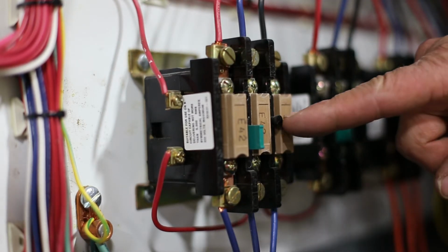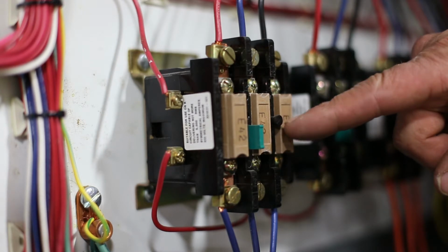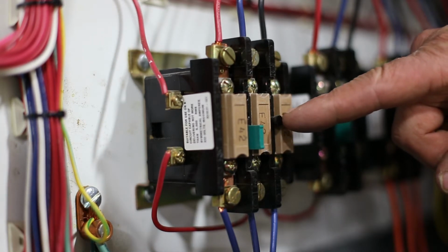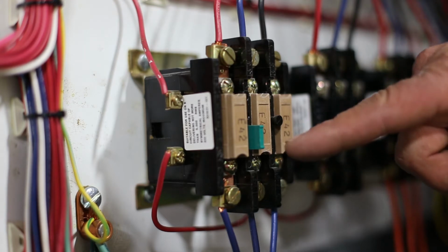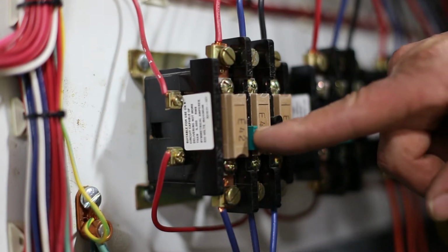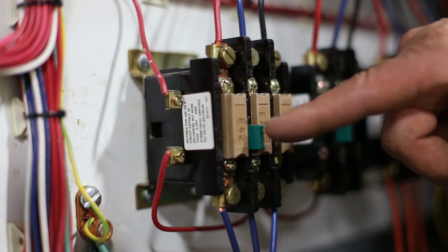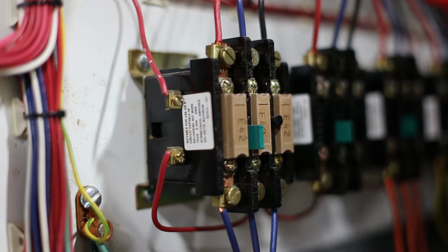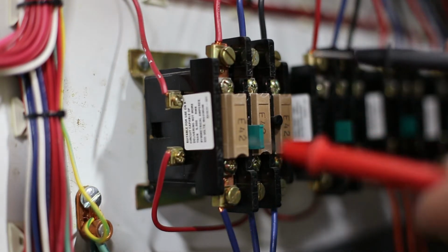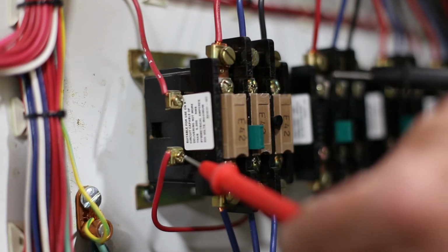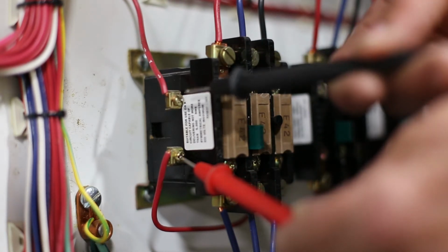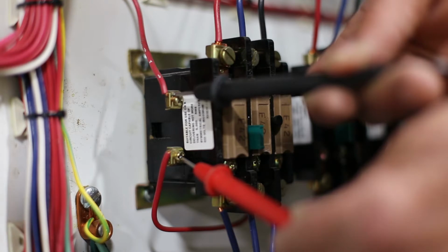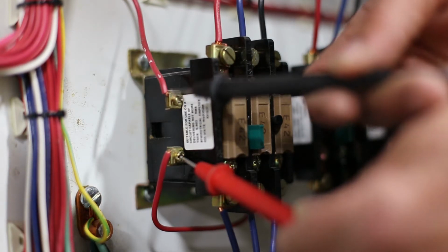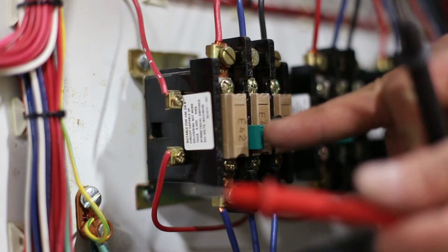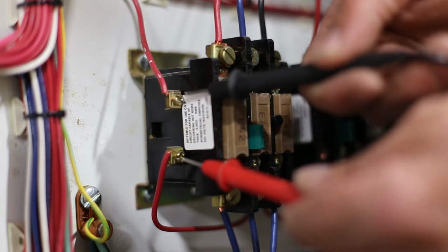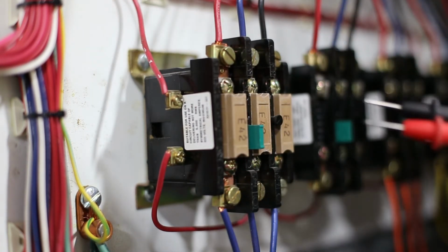You have a manual trip button here. It's a little black button, it's round. Whatever you do, do not hit that one. If you're going to reset an overload, press this green button here. On some of the older ones, they were red buttons. But if you want to check and see if an overload is good, you can ohm them out by going from the bottom terminal here on the left side to the top terminal here. If it ohms out, you are good. If it doesn't, your overload is bad, and if you press the reset button and it still does not ohm out, you're going to have to replace this overload.